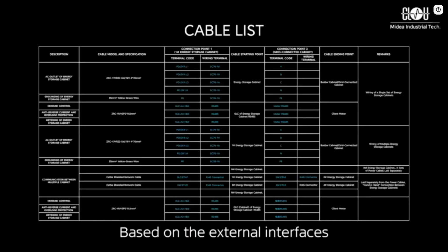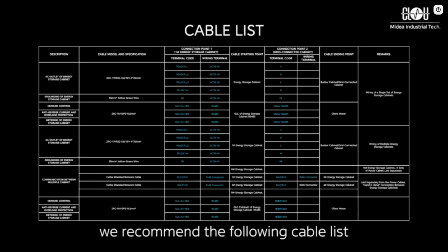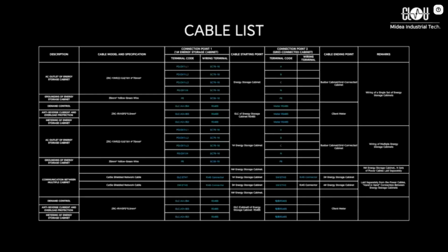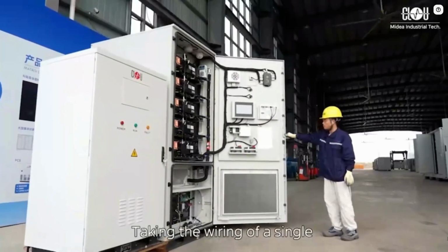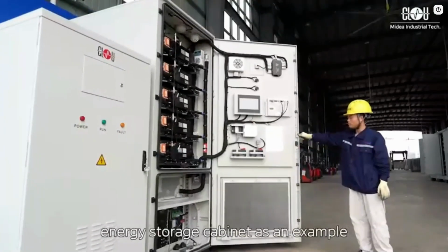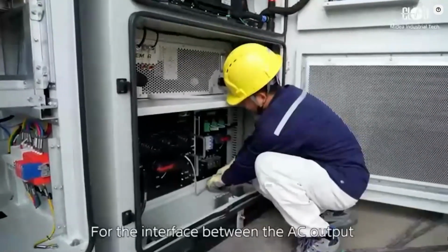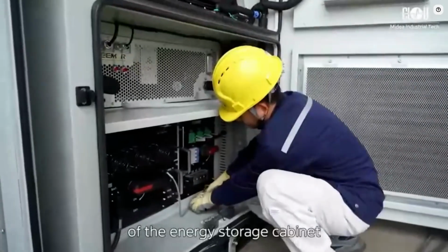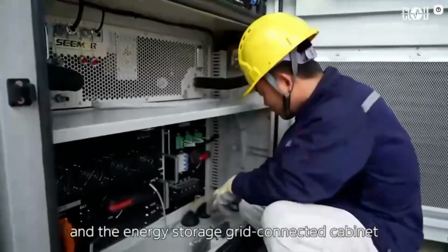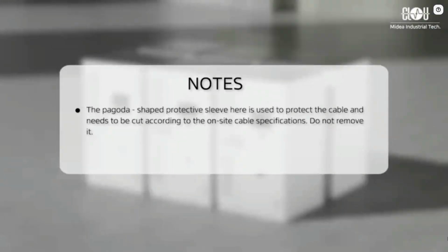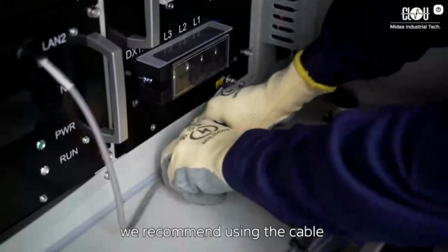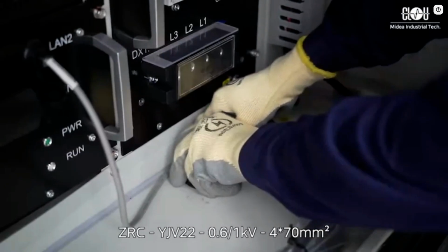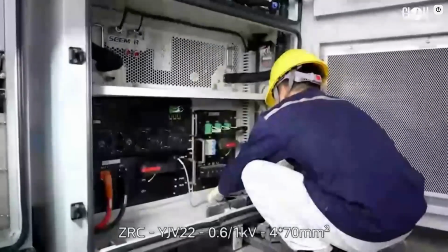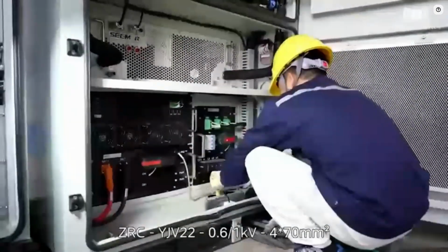Wiring of the energy storage system. Based on the external interfaces of different energy storage cabinets, we recommend the following cable list. Taking the wiring of a single energy storage cabinet as an example: for the interface between the AC output of the energy storage cabinet and the energy storage grid-connected cabinet, we recommend using the cable ZRC YJV22 0.6/1 kV 4x70 square millimeters.